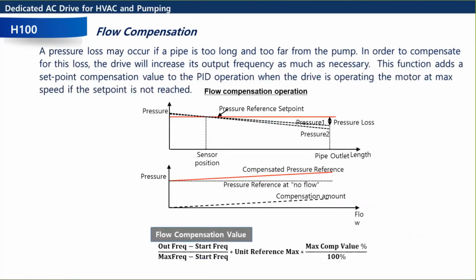This next one is flow compensation. This is most commonly also used in the irrigation market, especially when you have very long lengths of pipe, or if you're ever pumping on an incline. If you're ever going uphill, you're going to have a significant pressure loss. Or if you have very long pipe, that's also going to cause a pressure loss. Depending on where your transducer is, so your transducer would be your feedback device telling you what the pressure is in the line, and where your pump is, you may need to use flow compensation to compensate for the difference. In order to compensate for this loss, the drive will automatically increase the output frequency to boost up that pressure and compensate for the losses.